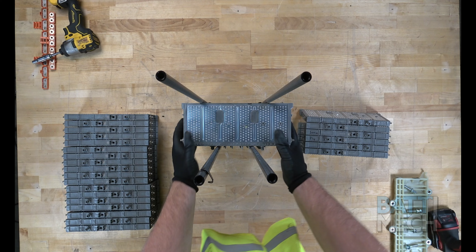Your BattMech batteries are individually tested to assess leaks, capacity, voltage, and internal resistance. The highest and lowest capacities are arranged to optimize the pack's performance and to minimize the differences in block voltage throughout the pack. Each pack is load tested at the same time, but BattMech monitors the voltage of each individual module when testing. Packs are tested under a high current load.